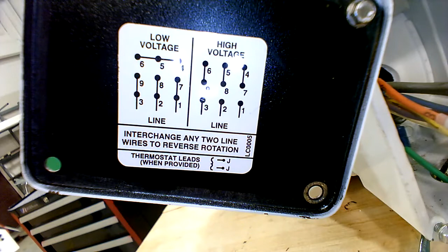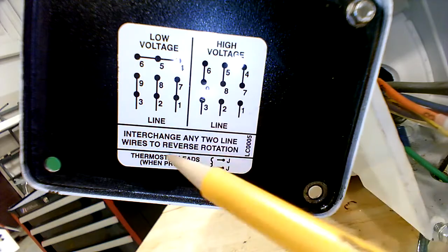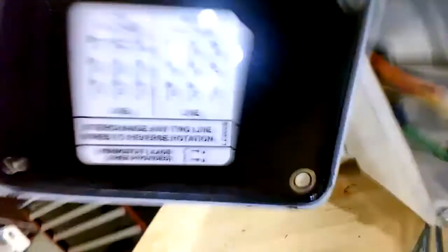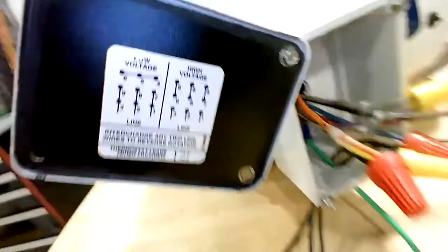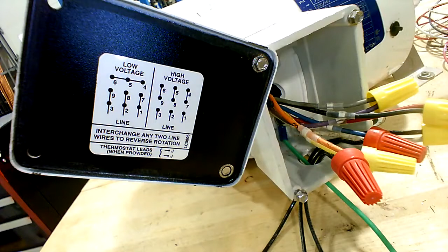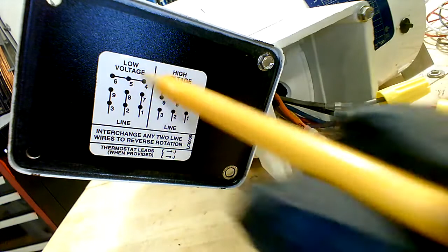Your 3 lines that come from the motor starter has a line 1 leaving at T1, it will come and join with 1 and 7 in this motor, giving you 3 wires together. Line 2 from the starter joins with 2 and 8 here, that'll give you 3 and a wire nut. Line 3 from the starter comes and goes with 3 and 9 in here, that gives you another 3 together. And then the 4, 5, and 6 come together in a wire nut and they're just insulated.